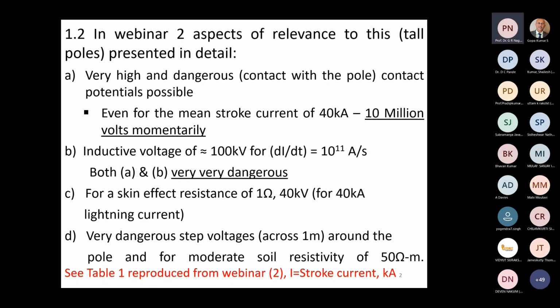The other aspect is the surge impedance. Surge impedance is what's offered by the inductance of the pole and the capacitance of the pole with respect to ground. It will be very difficult for me to go into detail on this concept, but in summary, a tower of a single pole can be expected to have a surge impedance of the order of 150 ohms. So even if a 40 kiloampere stroke occurs, the potential developed due to the surge impedance drop is of the order of 6,000 kilovolts or even more. Obviously, these volts are not small.